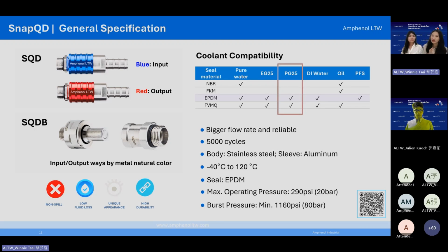I do notice something in the table. We're using EPDM for the seal. Is it because it works with the widest range of coolants, which includes the most commonly used PG25? Exactly. EPDM gives broad chemical compatibility for PG25 and other typical coolant, so you get consistent performance without changing fluids. Okay. And for SQD, you can also see that we've just mentioned the blue sleeve is used for inlet, the red sleeve used for outlet. So it is very easy to see and identify it at a glance.